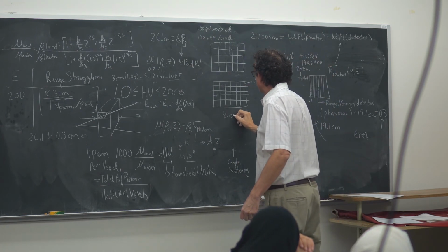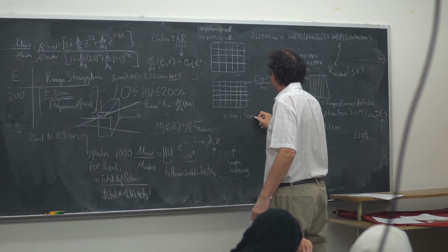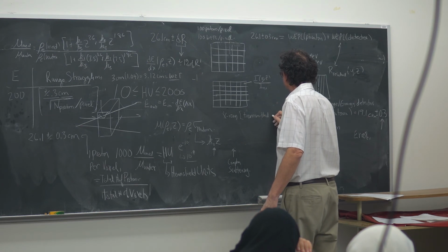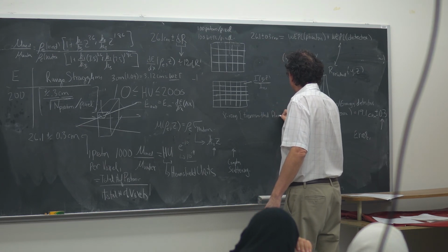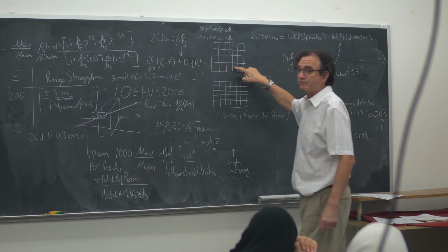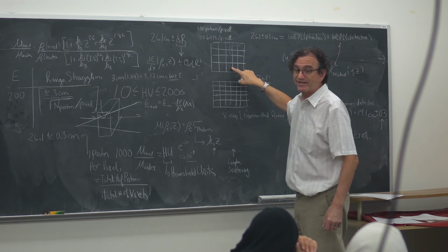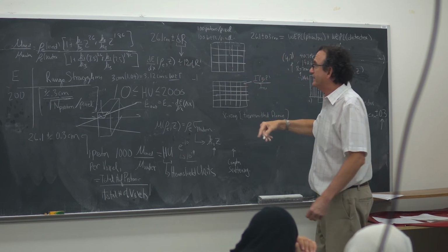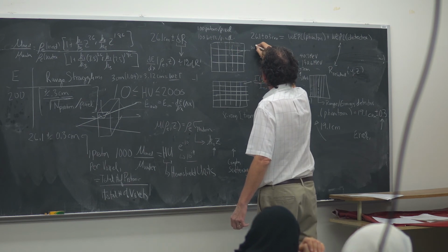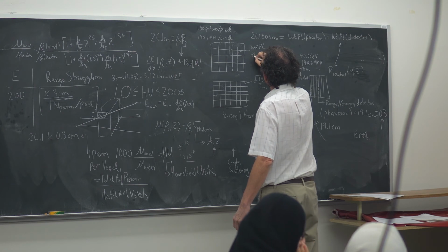So it's basically what you would call the transmitted fluence. With protons, the fluence is not changing very much. If a proton comes on the input side, it's going to get to the output side. But it does give you additional information, which is the water equivalent path length through the phantom.